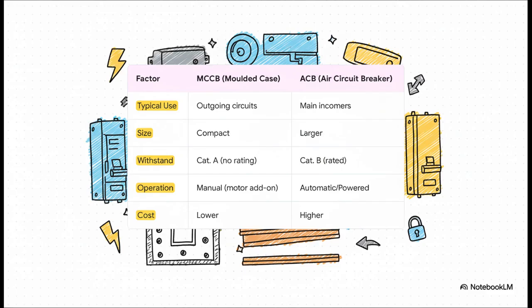MCCBs are your compact, cost-effective workhorses. They're perfect for the outgoing circuits that feed your sub-panels. ACBs, though, they're the big, beefy breakers designed to handle the massive power coming in right from the transformer. And a really key difference is that ACBs usually have a short time withstand rating, which is absolutely critical for making sure everything coordinates properly during a fault.